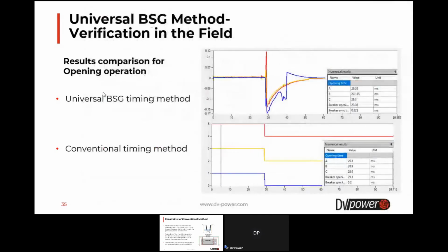The same principle for comparison and verification we use for the opening operation. As you can see, the algorithm detected opening time of about 29 milliseconds when the universal BSG timing method was applied, and pretty much the same results were obtained with the conventional timing method with very small deviations, which are about 0.2 or 0.3 milliseconds.